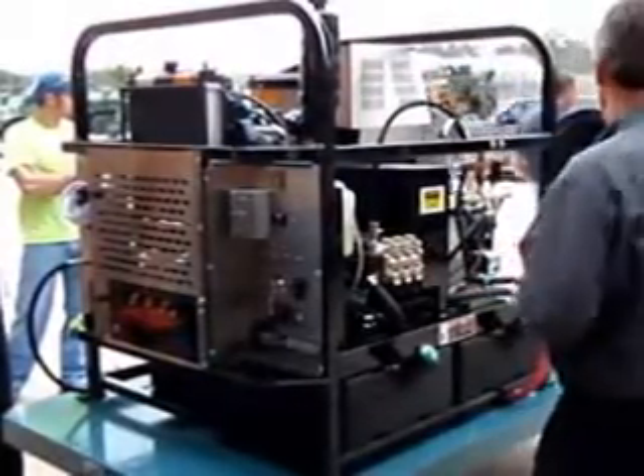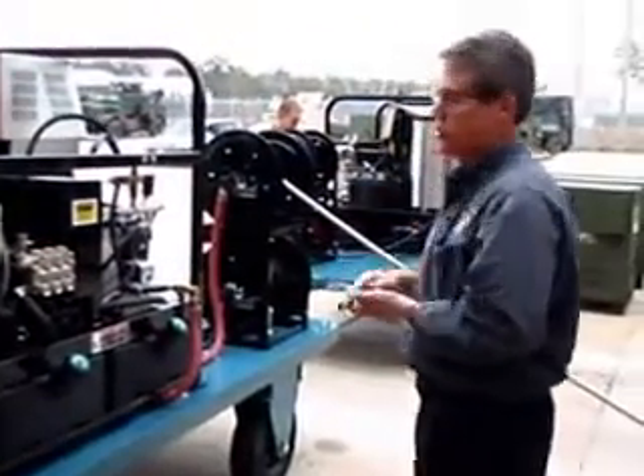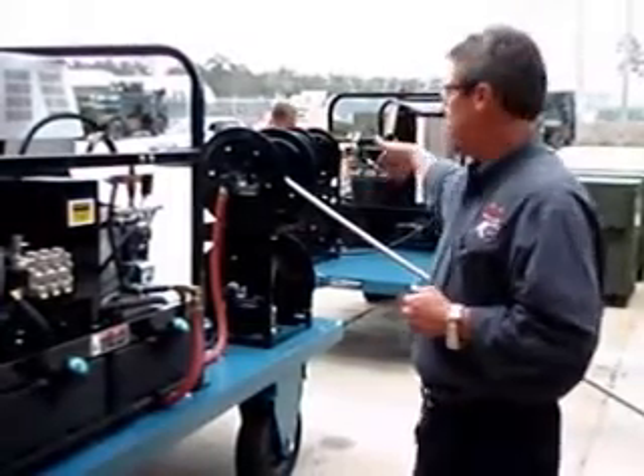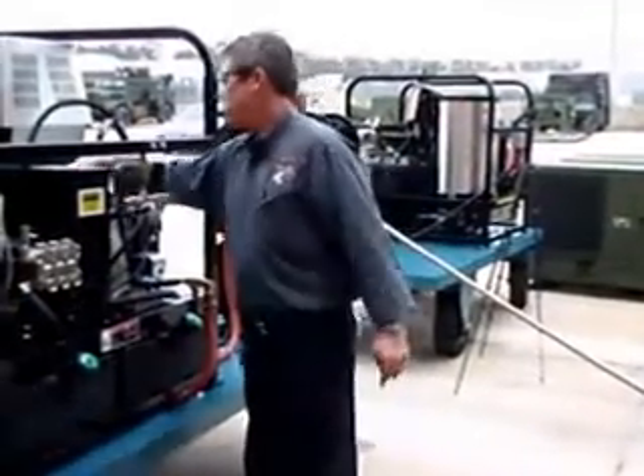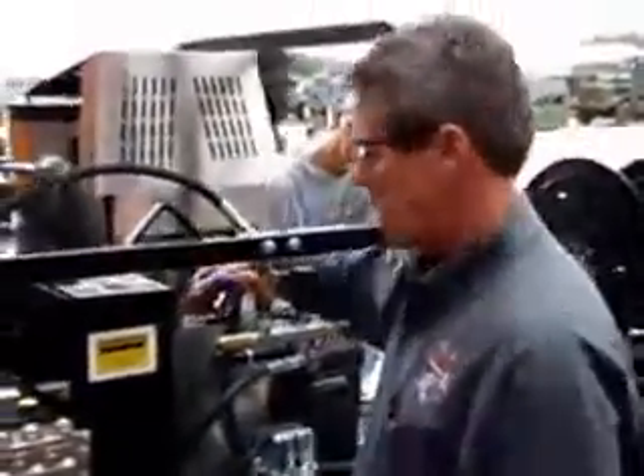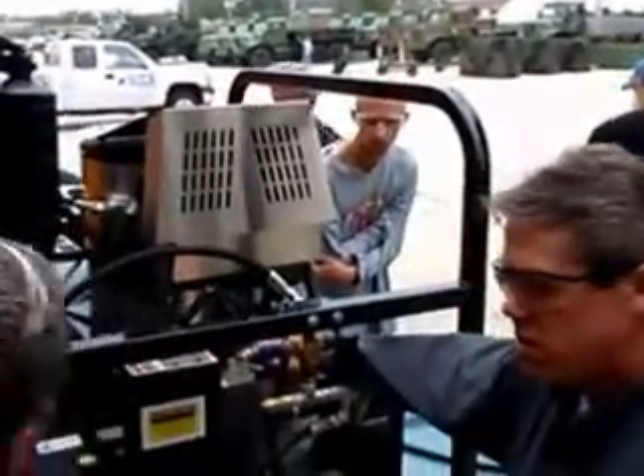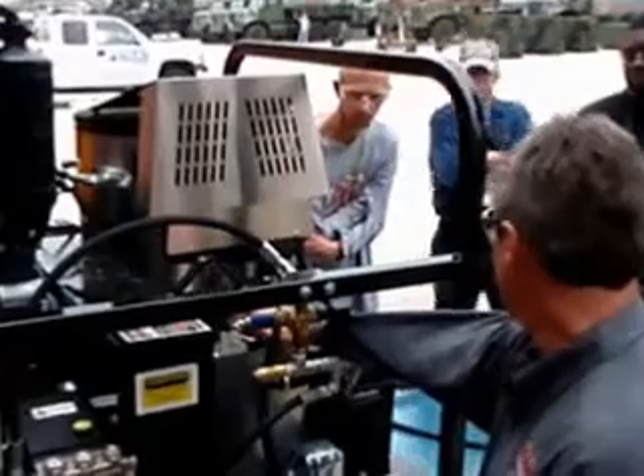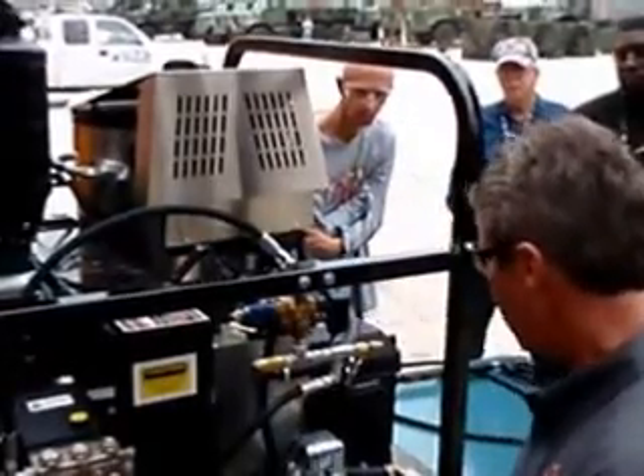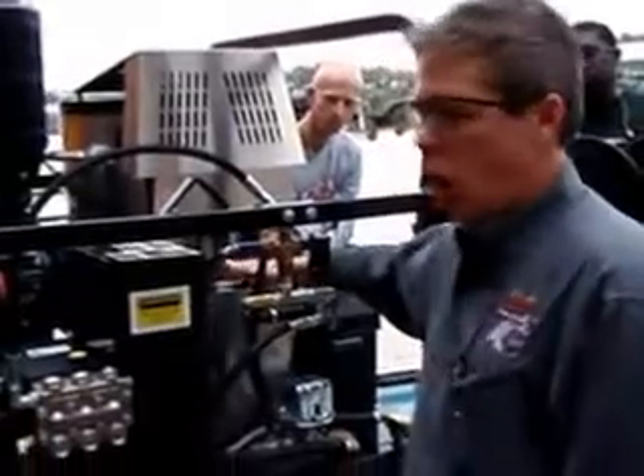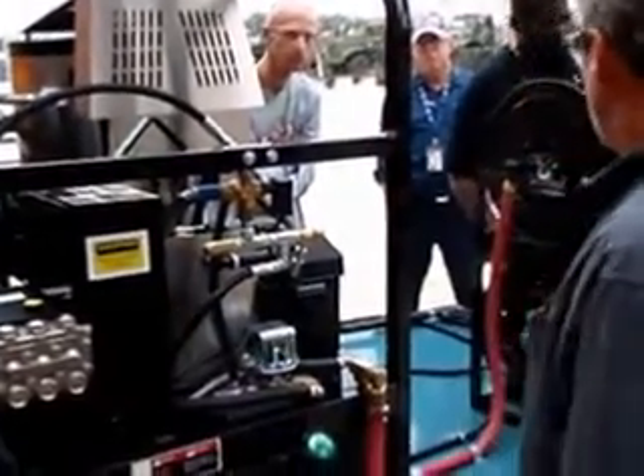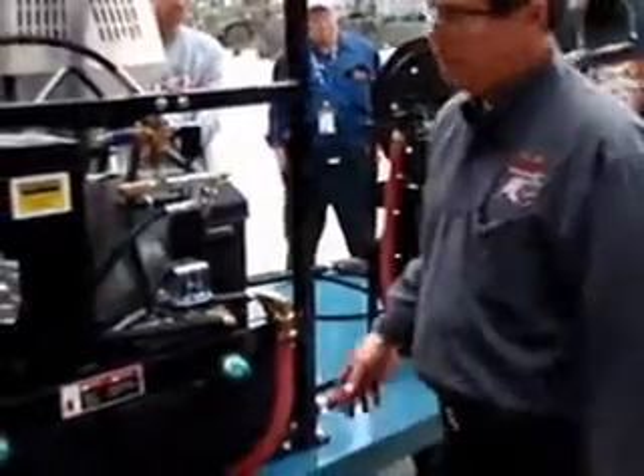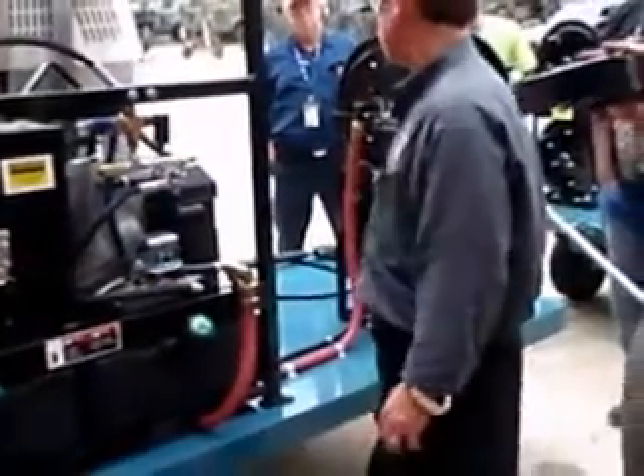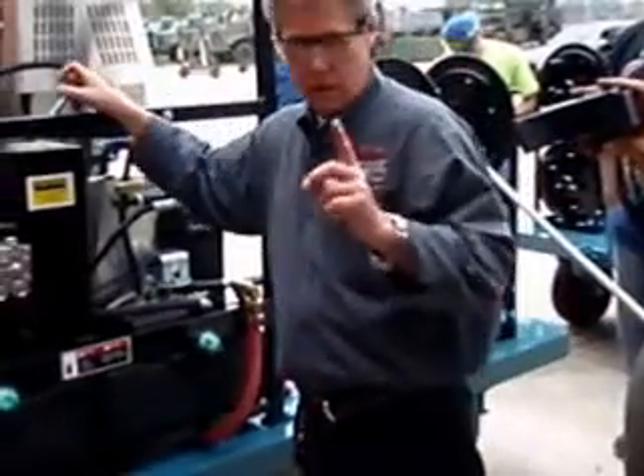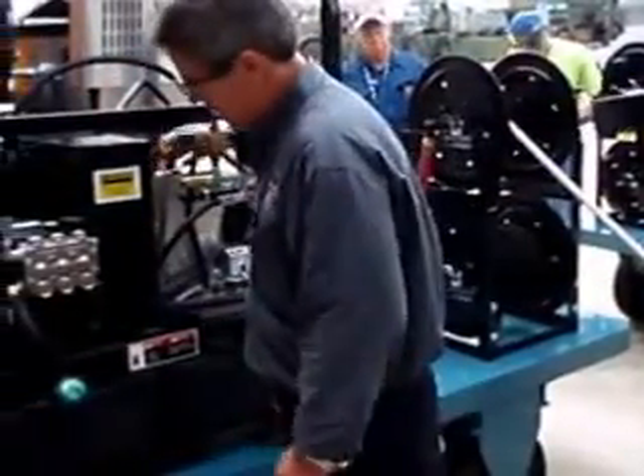As far as startup operation, first and foremost, make sure you have water feed to the system. How do you do that? Come over here and check your float valve. It's plastic, guys, so don't come over here with a hammer. All you've got to do is touch it. Just touch it - got water, we're good, go. That's all there is to it. Make sure you've got water flow. First and foremost, you want water feeding into this machine. If you don't have water feeding into this machine, I can guarantee you one thing: it's not going to work. Get water feeding into the machine, check it right there.